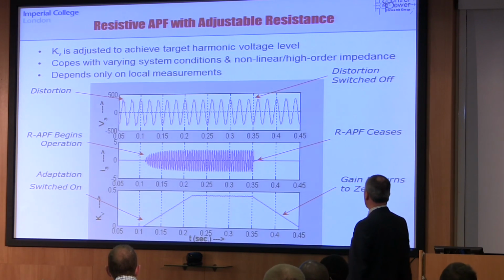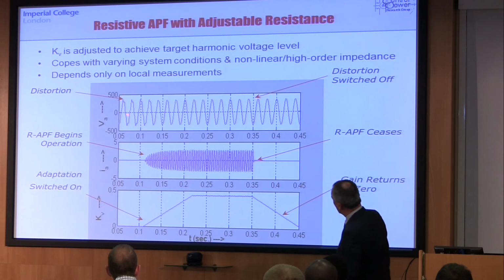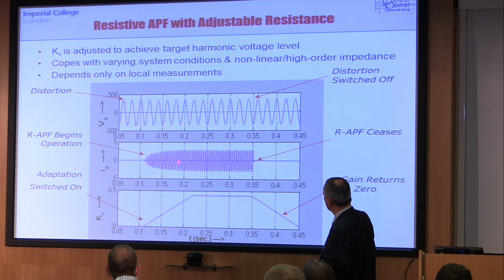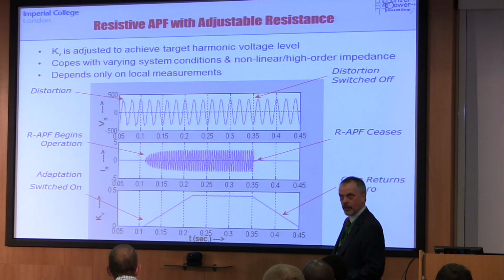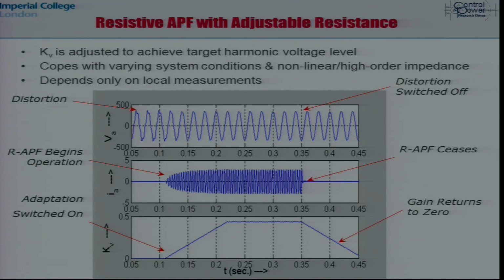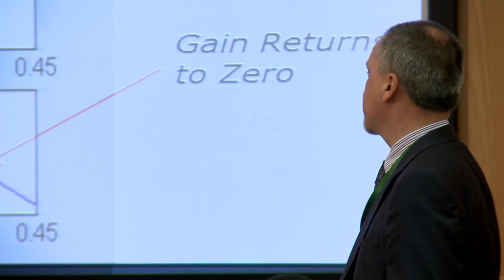Oh, sorry, I'd forgotten that I had a little illustration. That's a distorted set of voltage waveforms. This is the control loop cranking up the gain of the resistive compensator, and gradually you draw more and more harmonic current into the device, and that cleans up the voltage waveform. And if the locally distorting load goes away, then the current reduces almost immediately because the harmonic voltage driving it has gone away.